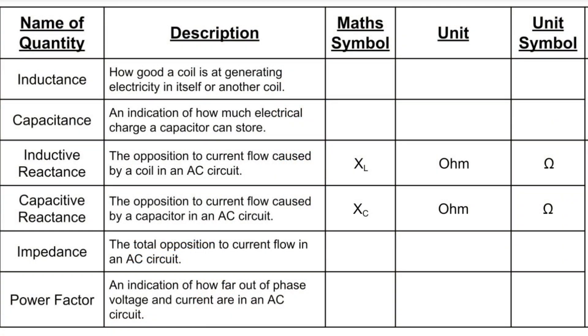Impedance is a really important unit for electricians because when you get out on site you might start doing some testing, and one of the tests you may do is an earth fault loop impedance test. The mathematical symbol we use for impedance is a capital Z. The unit is once again the ohm, since it is the total opposition to current flow in an AC circuit, and the unit symbol is the omega symbol Ω.